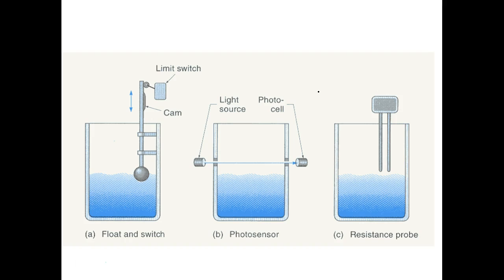When the level goes up, it triggers what we call a reed switch, using a stone magnet. This one works by passing a beam through the liquid — when the liquid rises, it blocks the beam, letting us know it's at a certain level. This one is a resistive probe, where we put a voltage across it, and as the liquid rises, it changes the resistance between the probes, letting us measure the level. Airplanes use a similar method — I don't know if this book covers it, but it should.